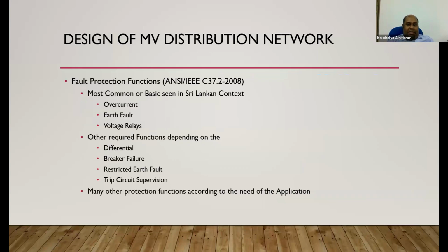Fault protection functions. If you take the ANSI protection code list, there are maybe more than 120 relay codes. Among them, in these building environments, we commonly practice very few relays, like overcurrent, earth fault, and voltage relays. Those are the very common relay types in the Sri Lankan context.